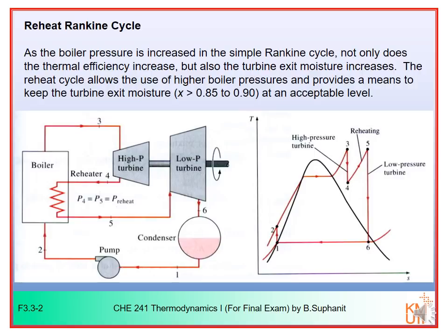The reheating scheme in the Rankine cycle uses a multi-step turbine. You will not expand the steam in a single stage turbine, but rather you expand from high pressure to intermediate pressure, and then you reheat the steam to a higher superheated temperature again, and then you expand further to low pressure. So you will have a reheater between two turbine stages.